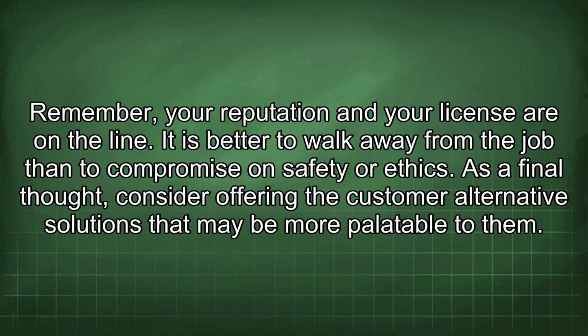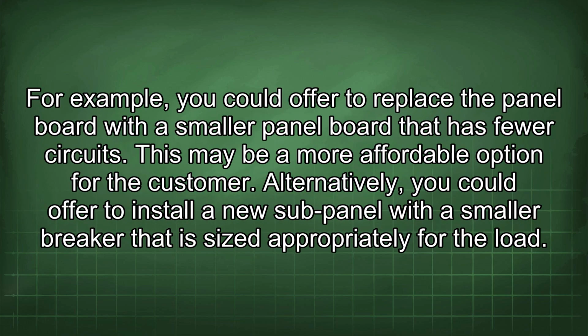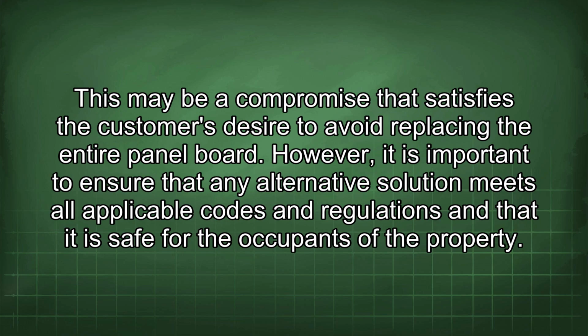As a final thought, consider offering the customer alternative solutions that may be more palatable to them. For example, you could offer to replace the panel board with a smaller panel board that has fewer circuits. This may be a more affordable option for the customer. Alternatively, you could offer to install a new sub-panel with a smaller breaker that is sized appropriately for the load. This may be a compromise that satisfies the customer's desire to avoid replacing the entire panel board. However, it is important to ensure that any alternative solution meets all applicable codes and regulations and that it is safe for the occupants of the property.